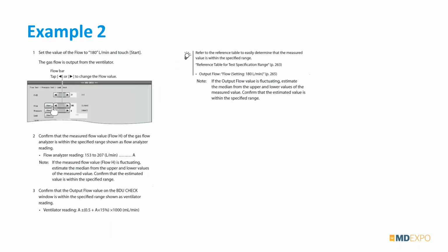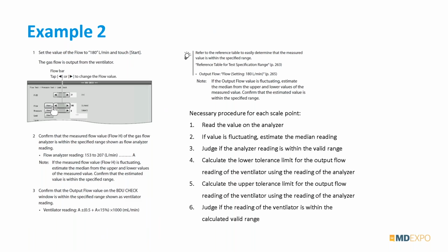Here's another example. This is from a different ventilator manufacturer. Here it's about the different flow scale points. So very often you have to do like 10 liters per minute, 20 liters, 50 liters, 100 liters and stuff like that. And here it's the same thing. You have to first do a setting on the ventilator and then measure it and then calculate the acceptable ranges with a percentage value and then interpret whether this is within the range or not. So it's pretty much the same story here. It's quite cumbersome and there's a lot of potential for misinterpretation here.